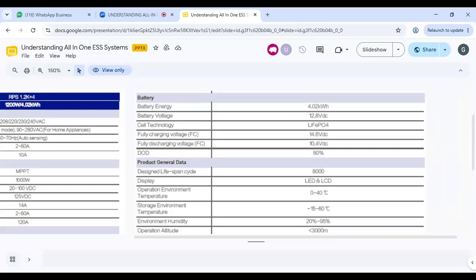So the battery energy, which is 4 kilowatts, this is 4.02 kilowatt hour. That's the capacity of the battery, which is lithium ion, as we know. Battery voltage is 12 volts, which is 12.8 volts. Cell technology is LiFePO4, which is a very good technology in terms of lithium ion batteries. It gives you peace of mind and the expected backup time all the time within its lifespan. So you can see the fully charged voltage of the battery is 14.6 volts, while the fully discharged voltage is 10.4. All this, the inverter will manage by itself.